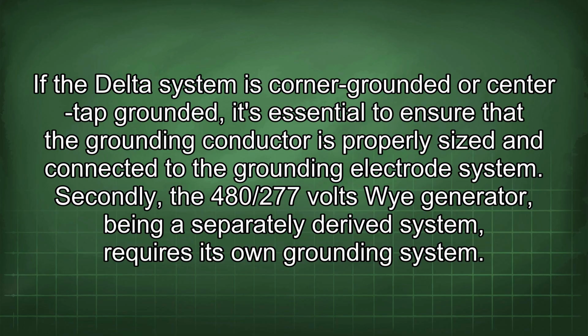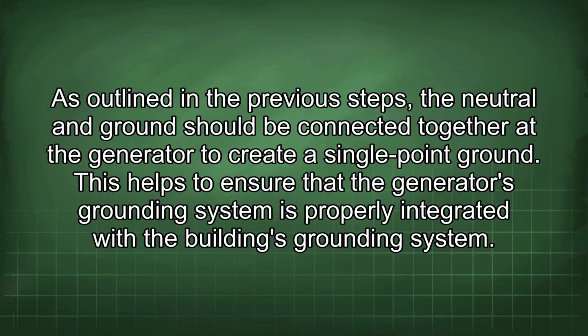Secondly, the 480/277 volts Wye generator, being a separately derived system, requires its own grounding system. As outlined in the previous steps, the neutral and ground should be connected together at the generator to create a single point ground. This helps to ensure that the generator's grounding system is properly integrated with the building's grounding system.